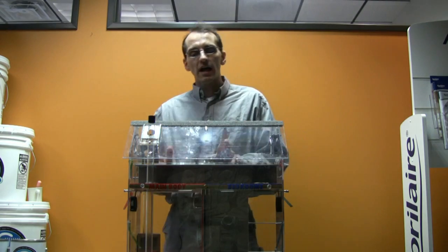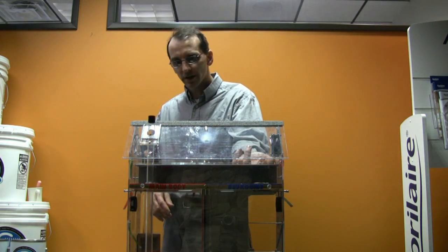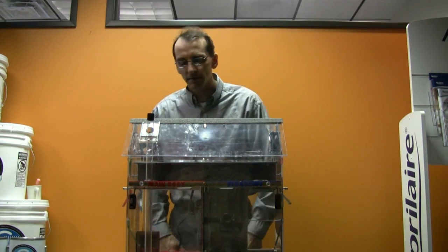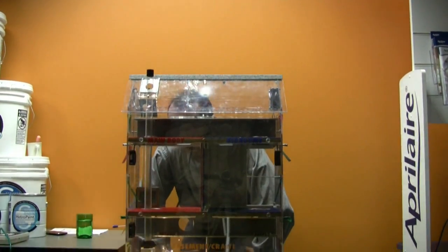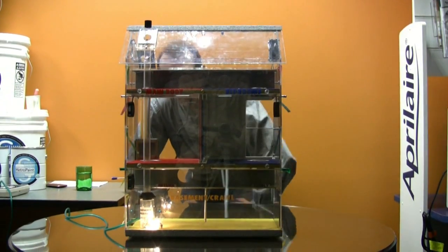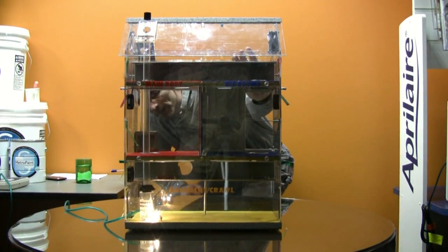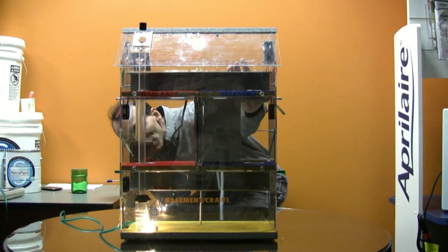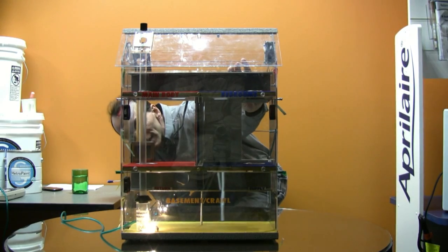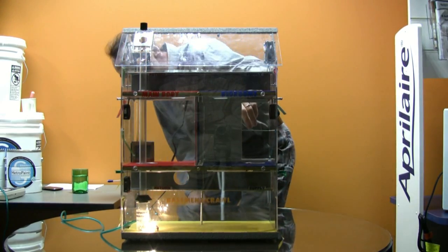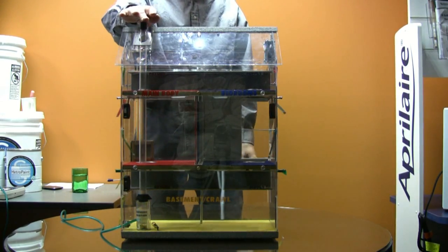So I can do a little visual for you here with some smoke in the water heater to actually show you. This is what we're talking about: instead of the smoke going up the chimney, it's being sucked out into the space all around it. Good thing you got a fan there.